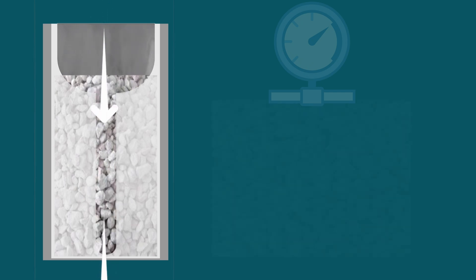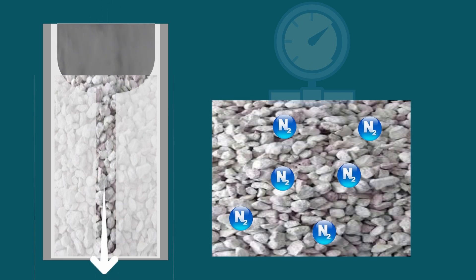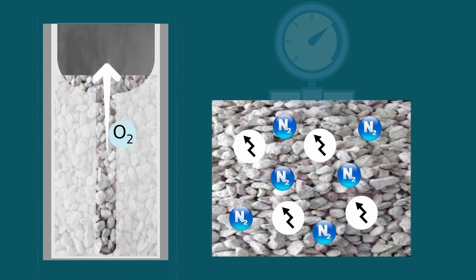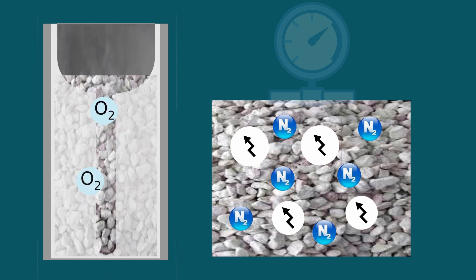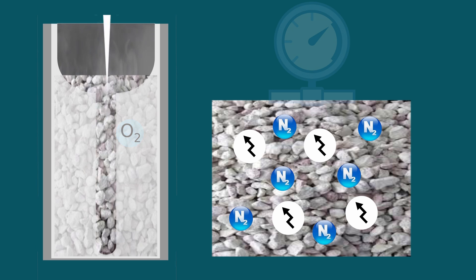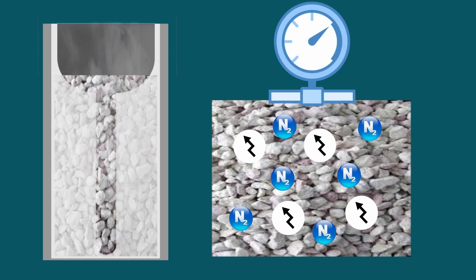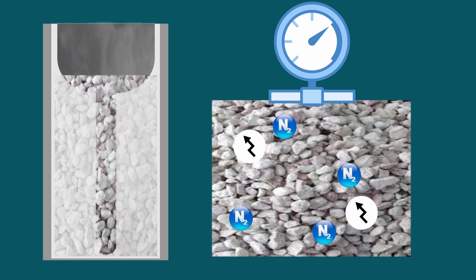The oxygen concentrator compresses the air and passes it over the zeolite, forcing the zeolite to adsorb nitrogen from the air. It then collects the remaining gas, which is mainly oxygen. Nitrogen is then desorbed from the zeolite under reduced pressure for further removal.